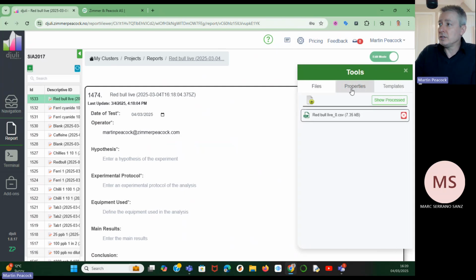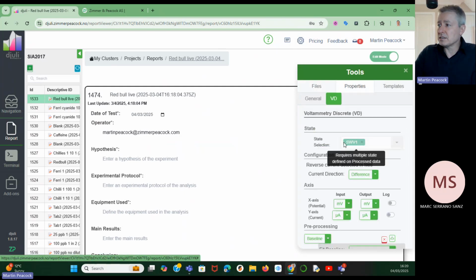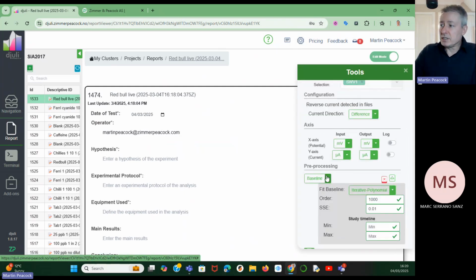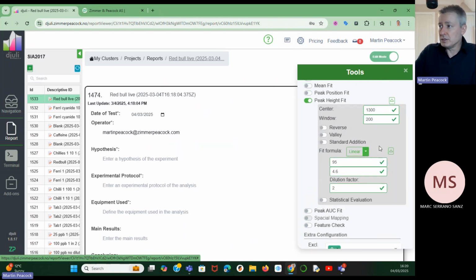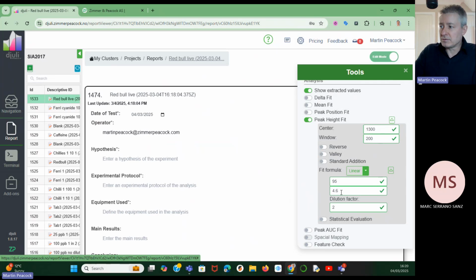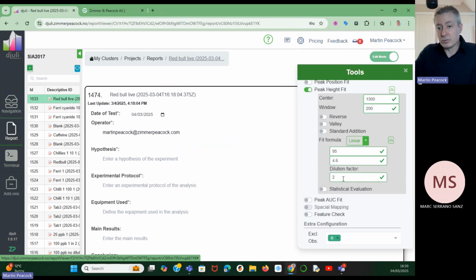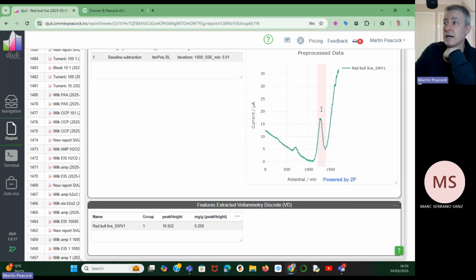And if I look in here under properties, I can see that we've done some pre-processing where we've done a baseline correction using an iterative polynomial. And I've just used the default values. I've told it what the calibration factor is. I told it where to find the peak height. And I've told it what calibration to fit to. It knows that the dilution was 2 because I added 1 volume plus 1 volume. So it's actually back calculated the whole sample and given me the caffeine in the original sample rather than in the diluted sample.